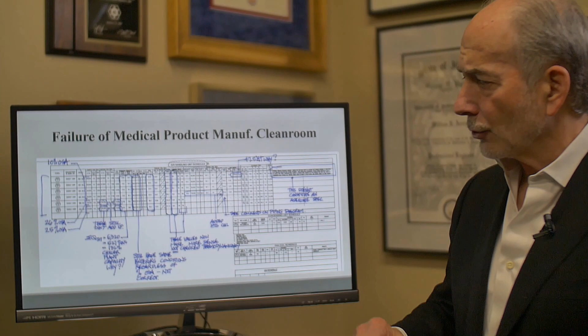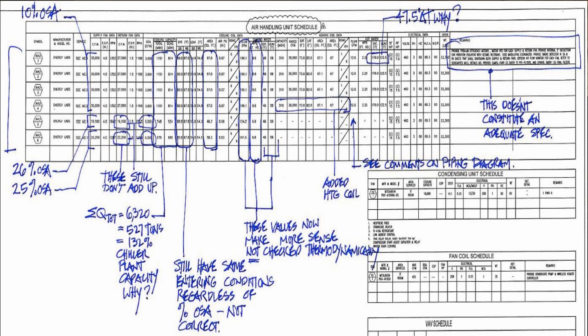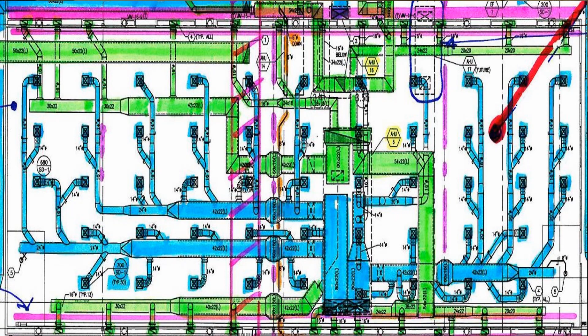The analysis I did showed that the air handling equipment the engineer had selected wasn't going to function properly. On top of that, they had a very complex duct system. As you can see here, the green is return ductwork and the blue is supply ductwork.